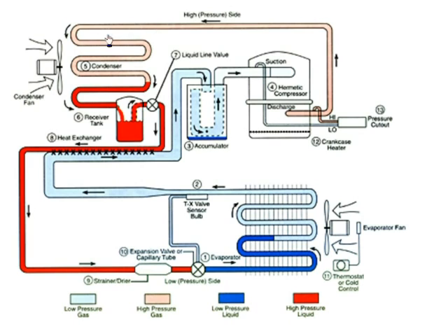But this one's a little trickier. If you're going to a TXV valve and you have to measure superheat or subcooling, you might want to go ahead and hook up your gauges for that. After you've kept notes on several of them, you could get to the point where you really don't need to hook up your gauges. You'll get it down pretty good. The problem with hooking up gauges is every time you screw it onto that service valve, you take a chance of a leak right there. So we want to eliminate the possibility of leaks.